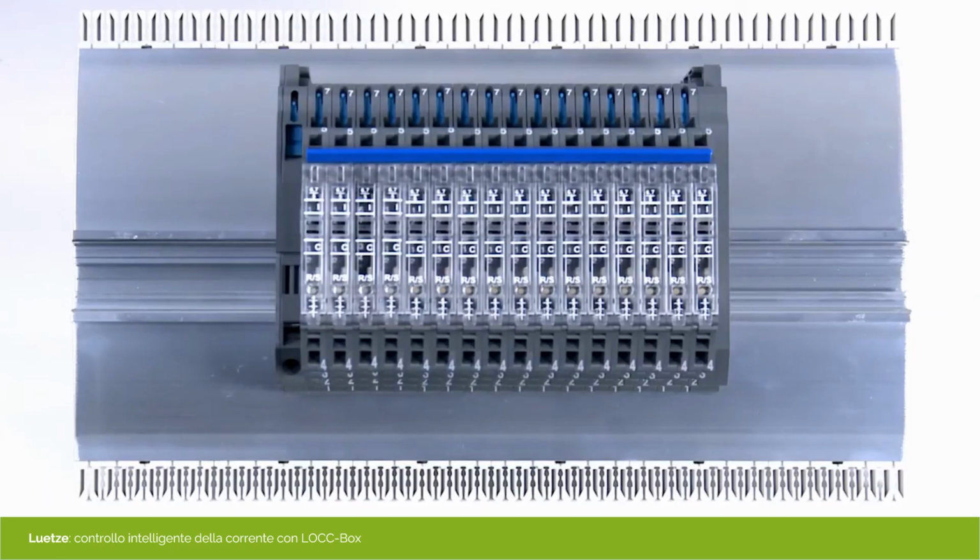The most important advantages over the circuit breakers are the reliable activation of capacitive loads and secure shutdown in the event of overloads and short circuits. In conjunction with power supplies that have a power boost, it is guaranteed that the system will trigger in the event of a short circuit in combination with short cable lengths. With longer cable lengths, the line resistance plays a part and the power boost function becomes ineffective.